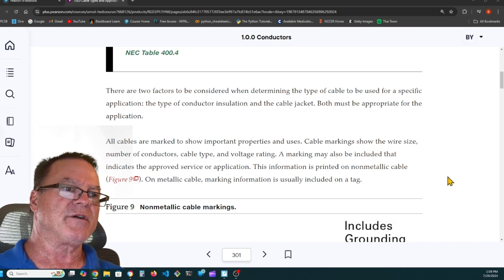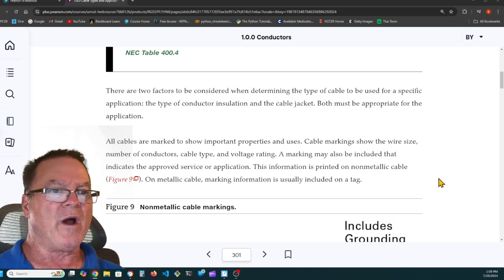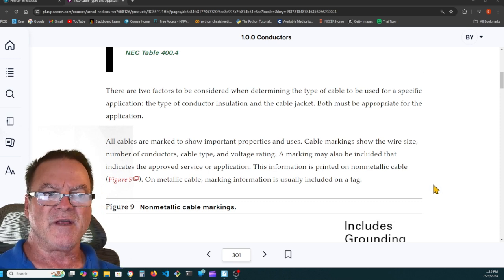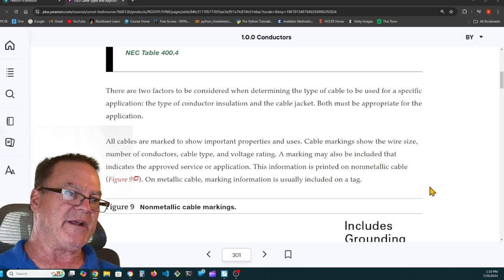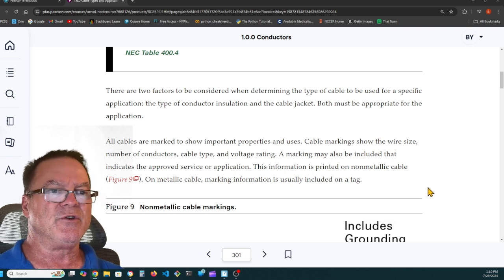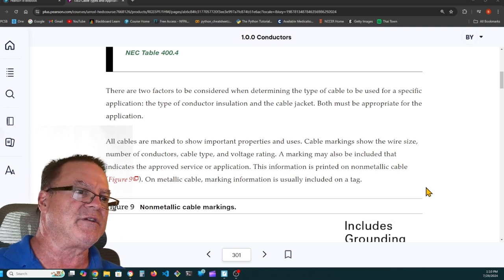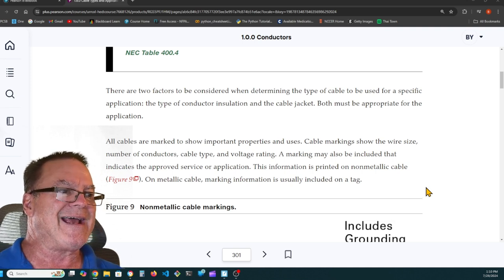All cables are marked to show important properties and uses. Cable markings show the wire size, the number of conductors, cable type, and the voltage rating. A marking may also be included that indicates the approved service or application. This information is printed on nonmetallic cable.